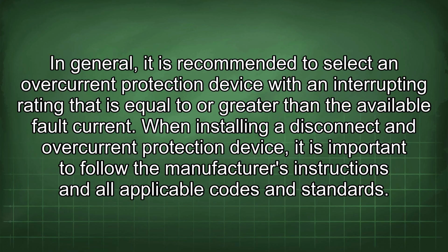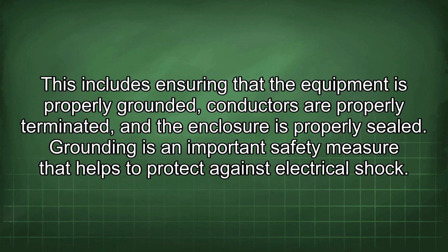When installing a disconnect and overcurrent protection device, it is important to follow the manufacturer's instructions and all applicable codes and standards. This includes ensuring that the equipment is properly grounded, conductors are properly terminated, and the enclosure is properly sealed.